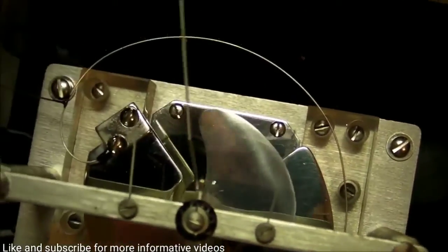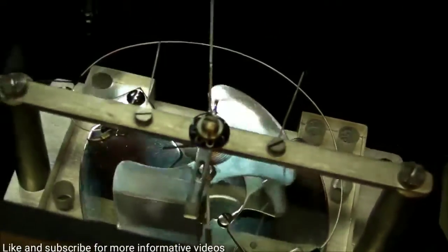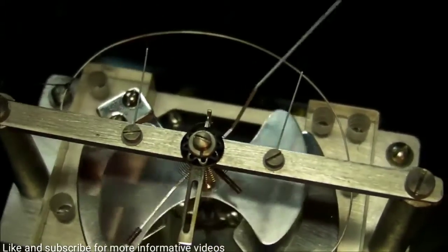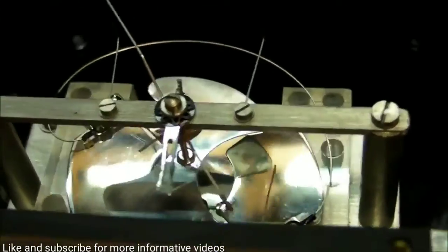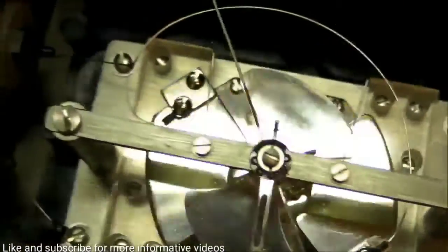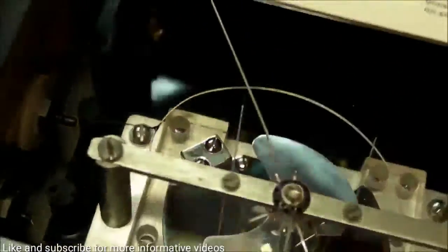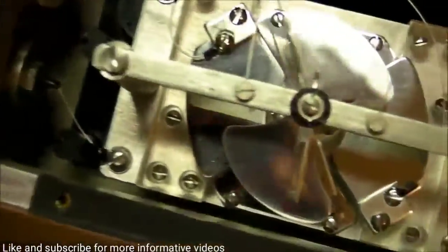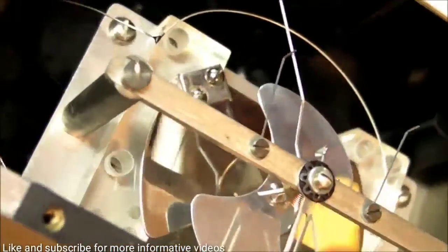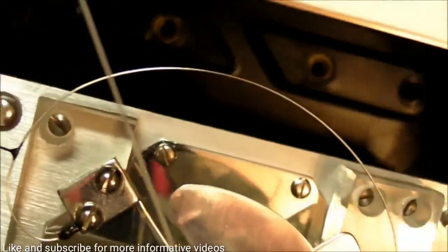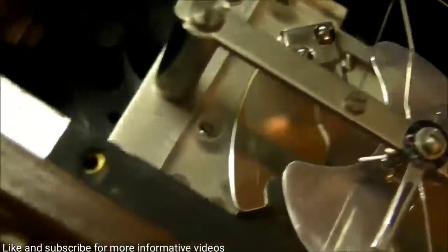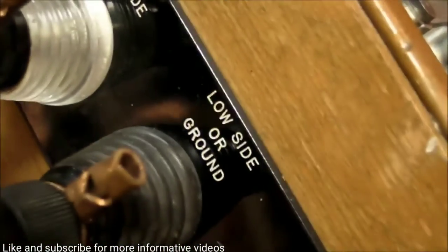So if I move the needle right here, you can see that the only moving part really is this one piece of aluminum in here that's got a couple of fin shapes on either side. And you might think that that's the part to be energized to high voltage, but no, it's actually part of ground, or at least the shield of the whole thing. You can see that it's got a metal shaft going from here down to the moving aluminum plate, and then continuing down to the bottom aluminum plate down there, supporting the whole structure.